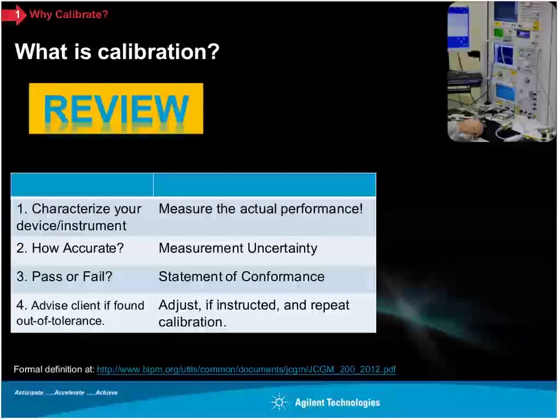Well, as soon as you have a measurement, then the first question that comes to mind is, great, how accurate was that measurement? And of course, as we mentioned previously, in the metrology world, we don't say accuracy. We refer to that as measurement uncertainty, generally expressed as a standard deviation when you take all errors into account. Okay, now you have a measurement. You know how good that measurement is with your measurement uncertainty.